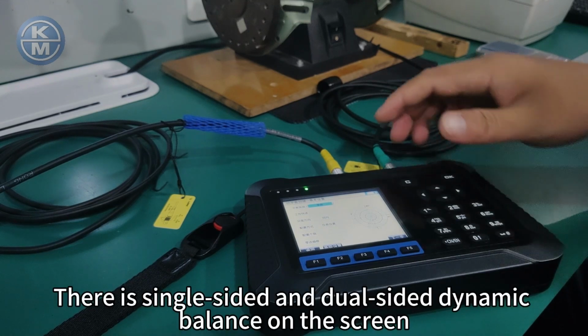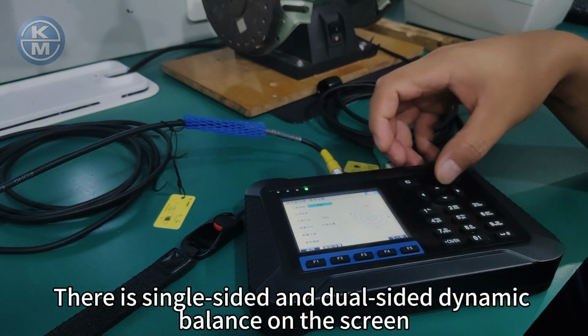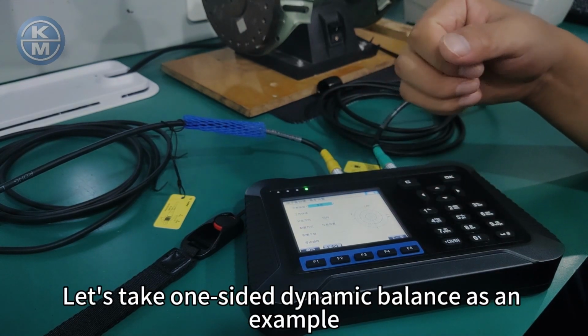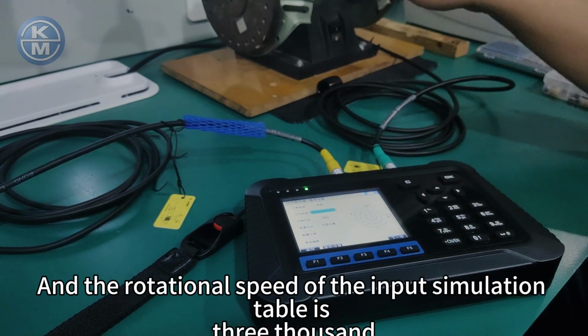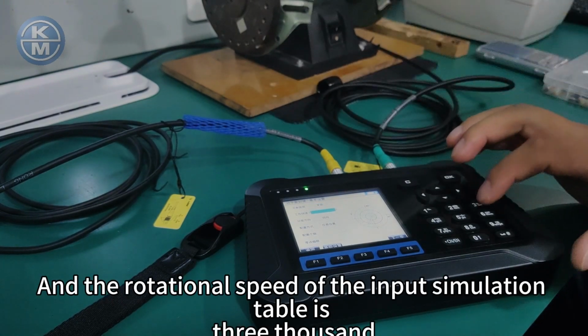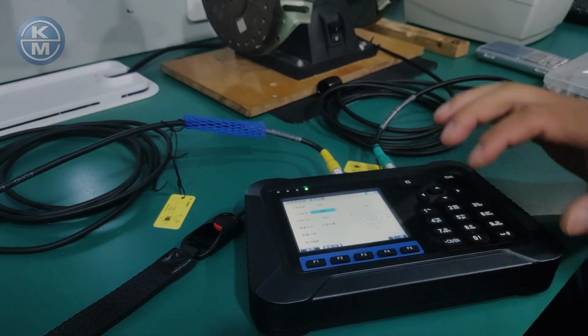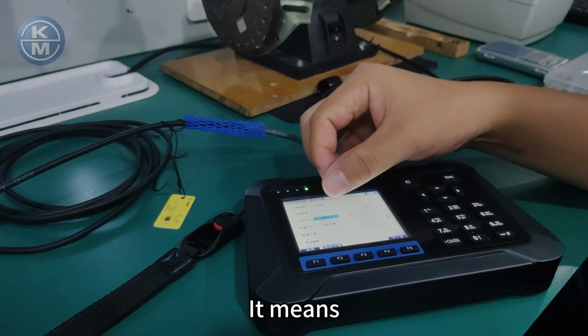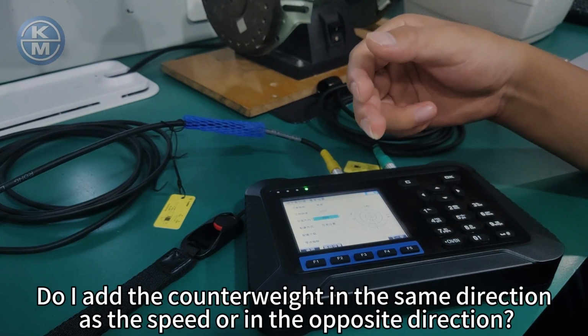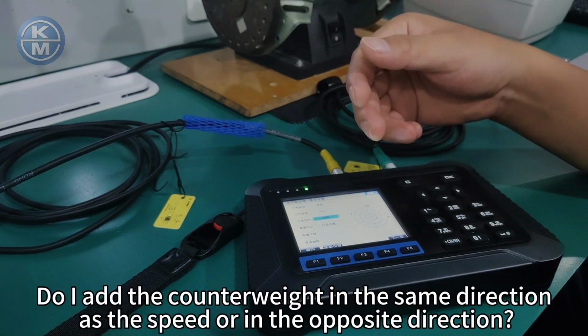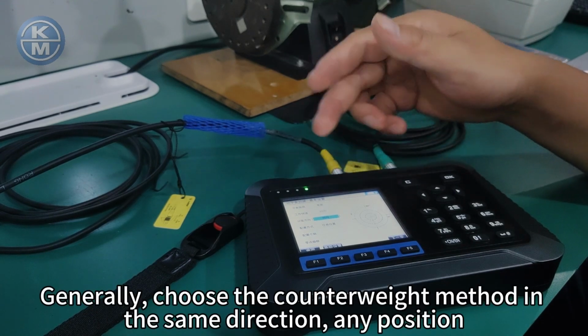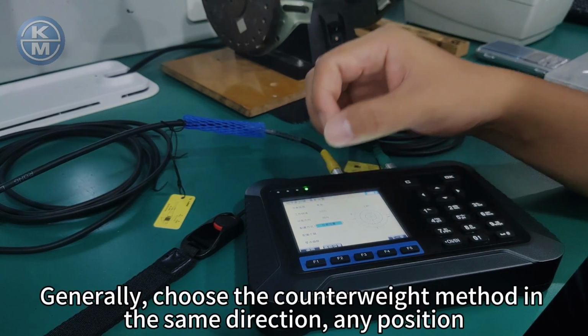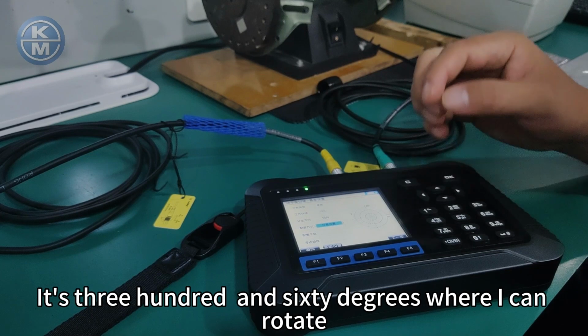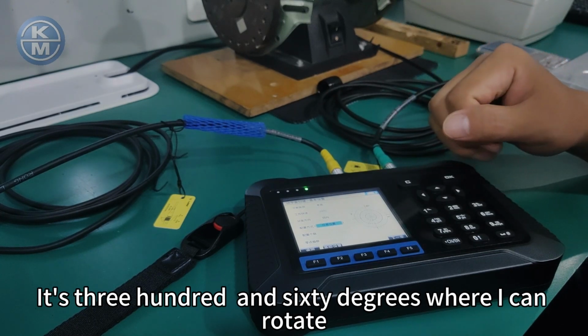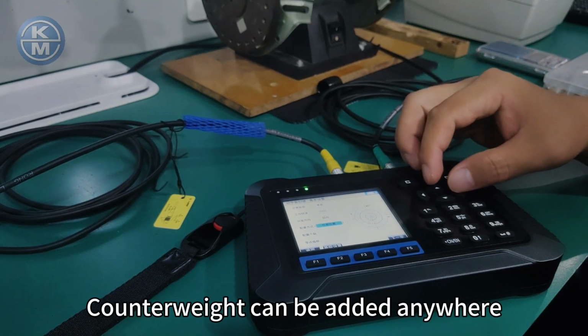There is single-sided and dual-sided dynamic balance on the screen. Let's take one-sided dynamic balance as an example, and the rotational speed of the input simulation table is 3000. Indexing direction means: do I add the counterweight in the same direction as the speed or in the opposite direction? Generally, choose the counterweight method in the same direction, any position. It's 360 degrees where I can rotate. Counterweight can be added anywhere.